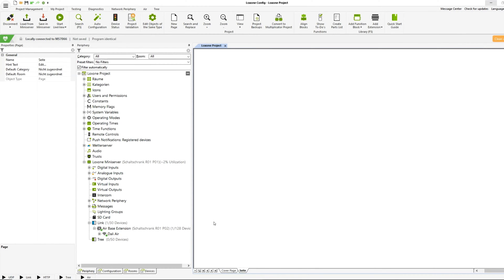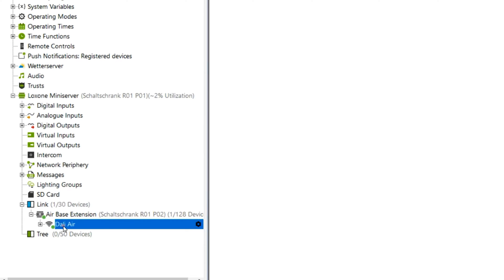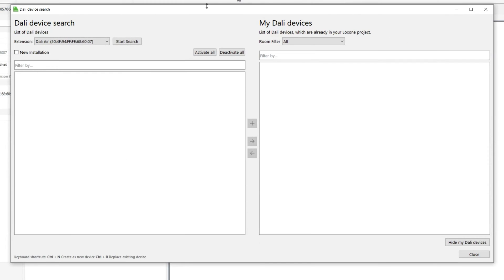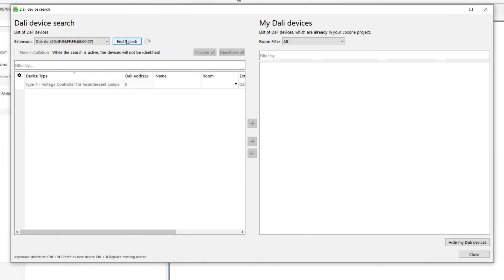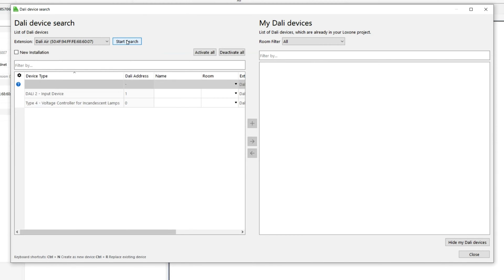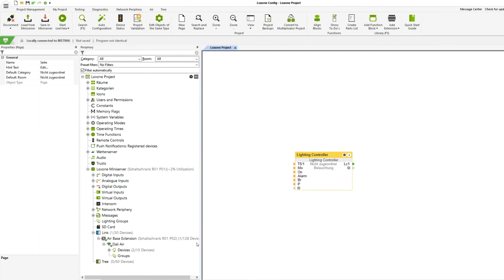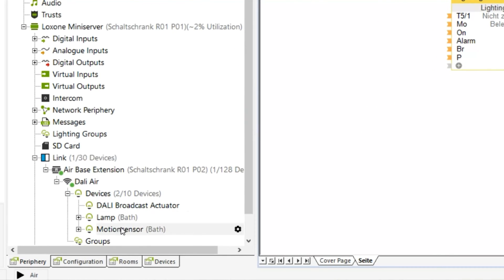Once the Dali Air has been successfully taught in, the DALI search can be started. In a new installation, the 'complete new installation' checkbox must be activated so that all DALI devices are re-addressed during the search. If the DALI extension is installed into an existing DALI installation, a normal search is sufficient to take over all DALI devices and their settings. Start the search with 'Start Search' and all connected DALI devices not yet included in the programming are listed. Once the search is finished, mark a device and it identifies itself by making all outputs pulsate. This way you can assign and name the devices accordingly — mark a device, choose designation, room and installation location, add them with a plus sign, and save the configuration in the mini server. Done.